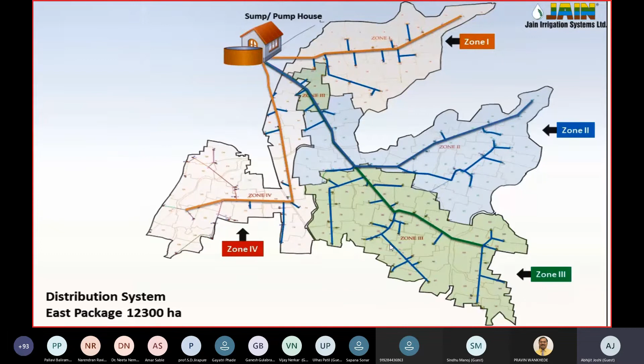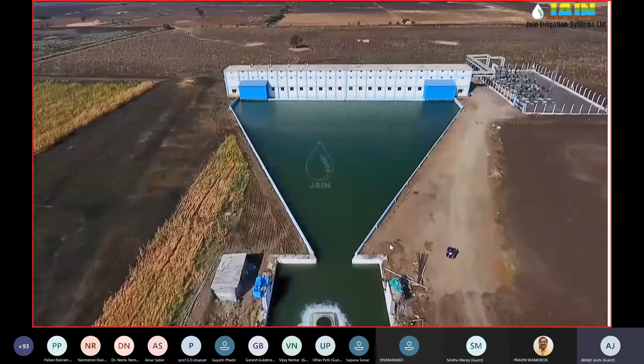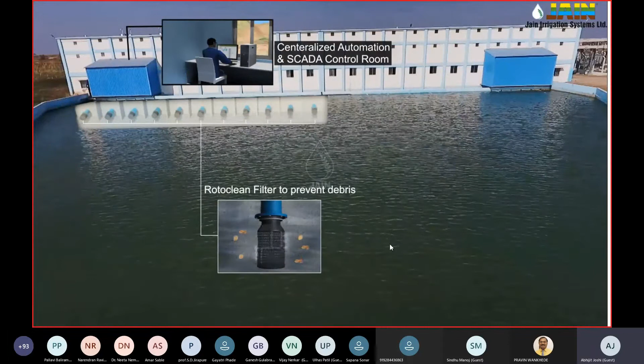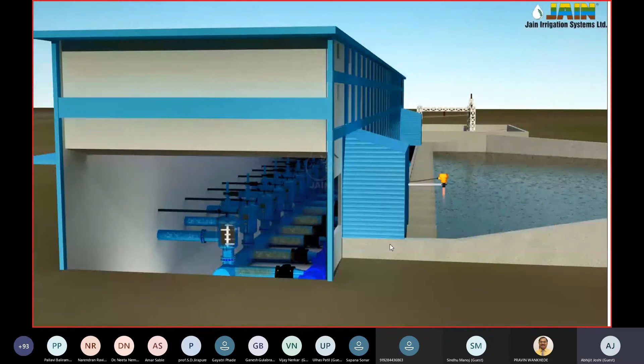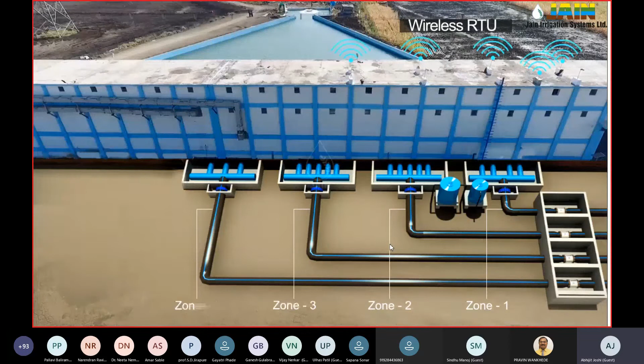Water from River Krishna is lifted from Narayanpur Reservoir to Stage 1 and flowed to Stage 2. Then from Stage 2 of West Main Canal to the sump of Ramthal Drip Irrigation Project. At the sump, water is pre-filtered through advanced Rotoclean suction filter to prevent large debris coming to the pumping machinery. Each zone has its own pumping station. There are 12 energy-efficient pumps. All pumps are operated through a variable frequency drive or VFD. Advanced SCADA system controls the operation of pumps on the basis of feedback received from pressure and flow sensors.